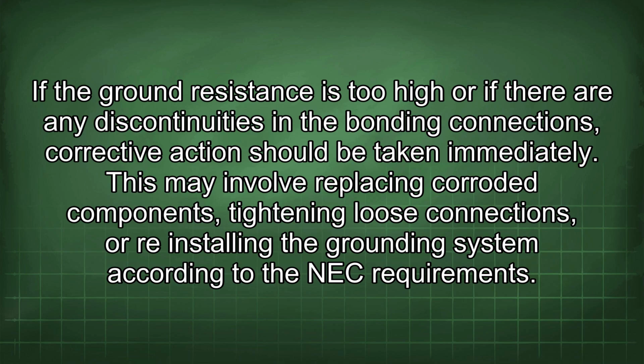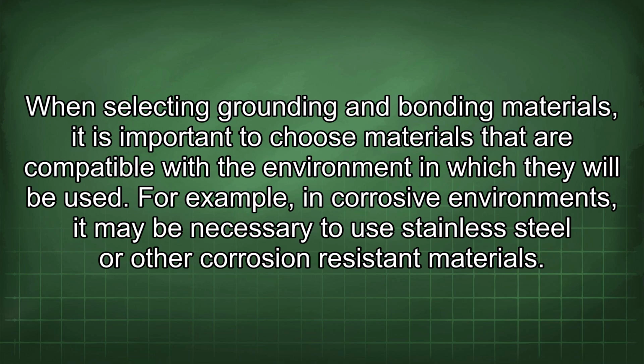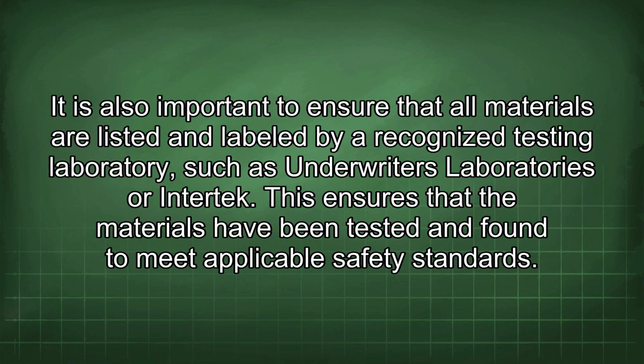NEC requirements. When selecting grounding and bonding materials, it is important to choose materials that are compatible with the environment in which they will be used. For example, in corrosive environments, it may be necessary to use stainless steel or other corrosion-resistant materials. It is also important to ensure that all materials are listed and labeled by a recognized testing laboratory, such as Underwriters Laboratories or Intertek. This ensures that the materials have been tested and found to meet applicable safety standards.